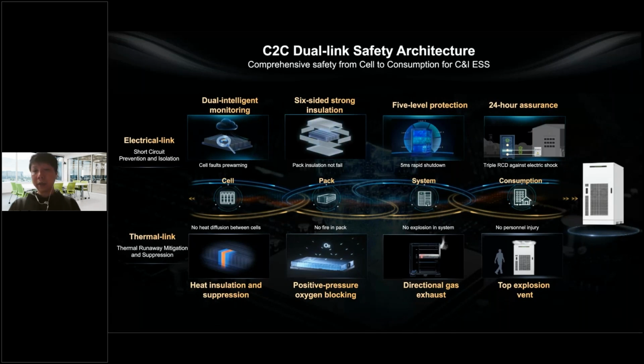And one last designing is top explosion venting. This feature is just in case all those other features fail and there's a fire happening inside the cabinet. Our system will have the top explosion venting, which means the pressure will be released from the top instead of from the front. Because when there's a fire, there's personnel or firefighters checking on this ESS, so releasing pressure from the top means there's no potential risk of causing injuries to the personnel. But if you release pressure from the front, that might cause injuries to the personnel when checking on this ESS. So this is also a very unique designing from Huawei ESS.